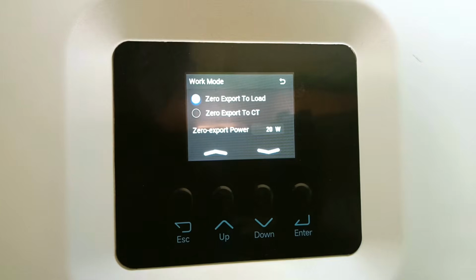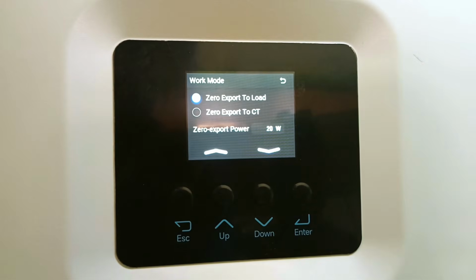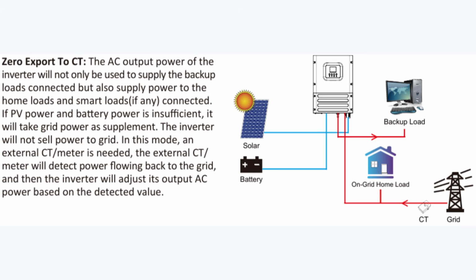CT is the current transformer. We talked about the CT in my first unboxing and specifications video. 0 export to CT. The AC output power of the inverter will not only be used to supply the backup loads connected, but also supply power to the home loads and smart loads, if any, connected. If PV power and battery power is insufficient, it will take grid power as supplement. The inverter will not sell power to grid. In this mode, an external CT meter is needed. The external CT meter will detect power flowing back to the grid, and then the inverter will adjust its output AC power based on the detected value.